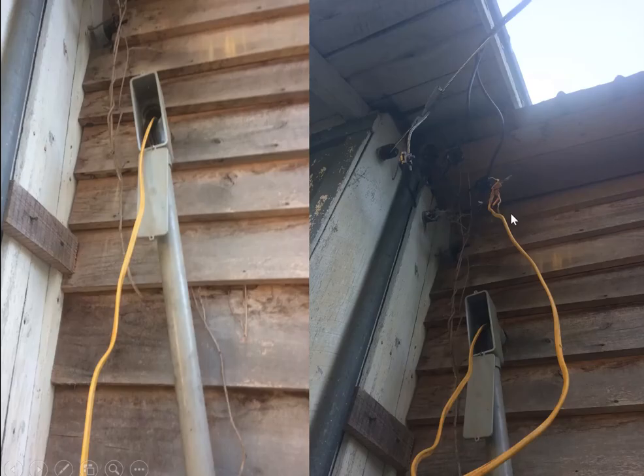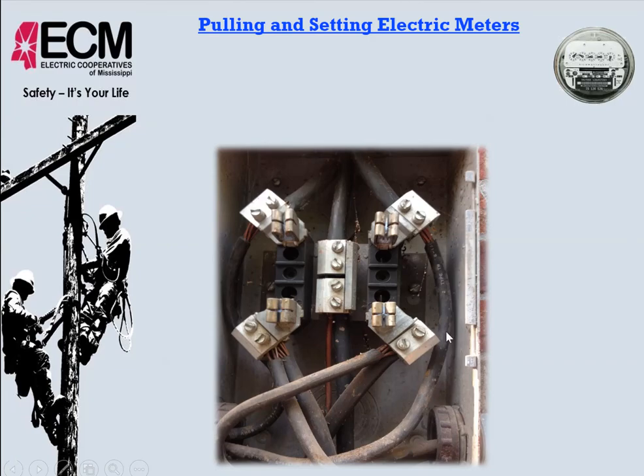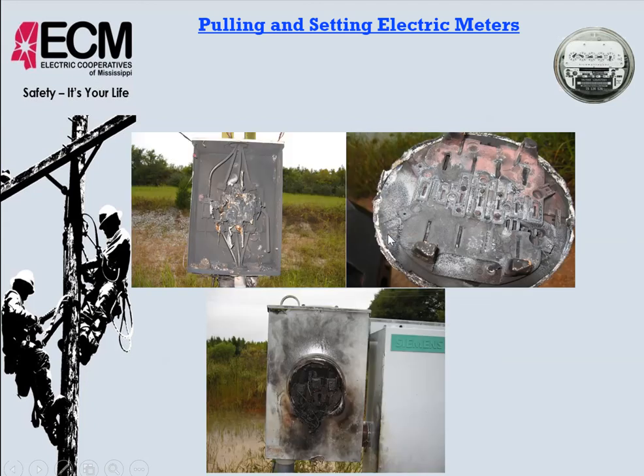Okay, hooked on the weather head, running this LB right there. Took the cover off, running in the house. This one right here, you have to look. There's a lot going on here. So we have our line side comes in, but they also have some that comes off the line side and goes in that pipe. Okay, it's not going to another meter base. If it were, we would have another weather head. So they're stealing there. So pay attention to things like that. Should only be the wire going to the weather head hooked to the top side.